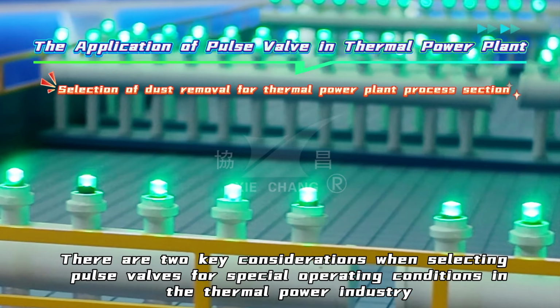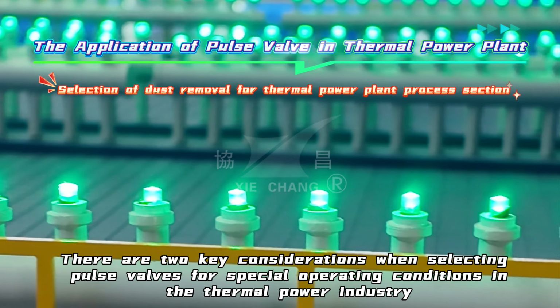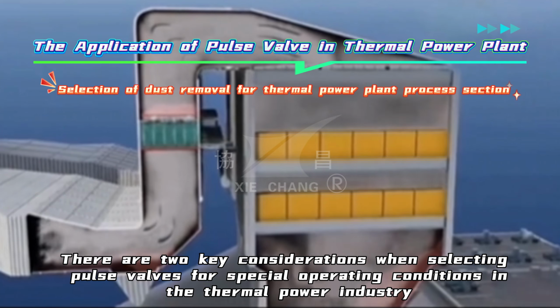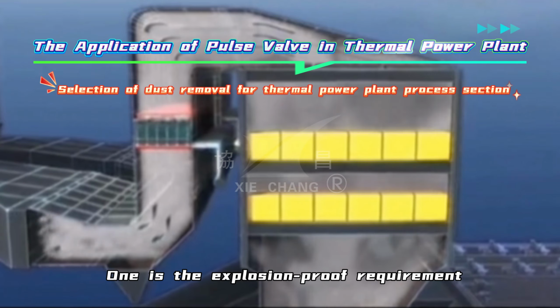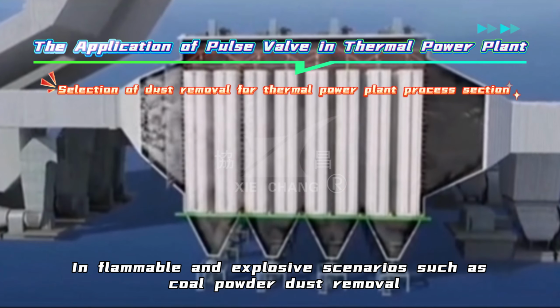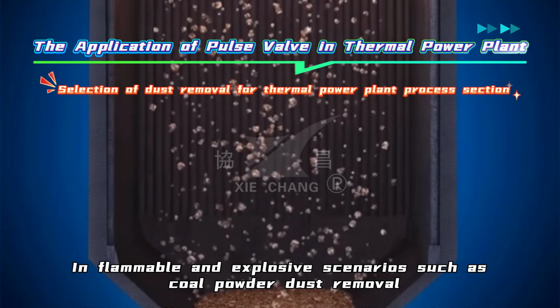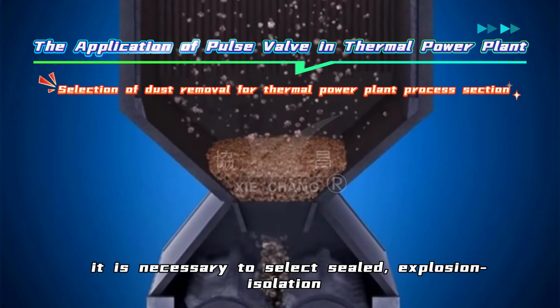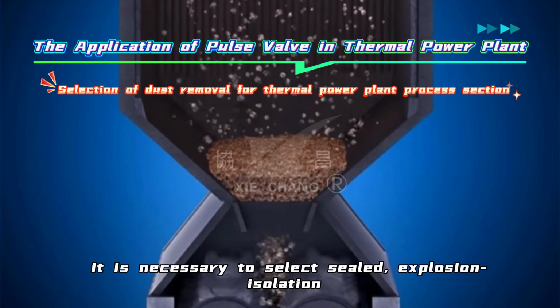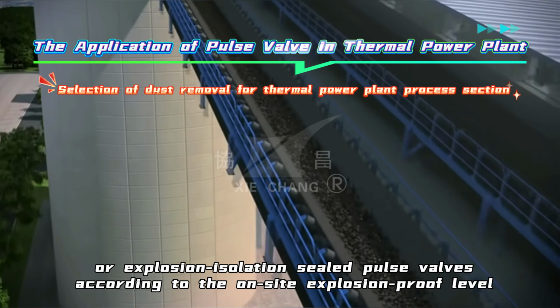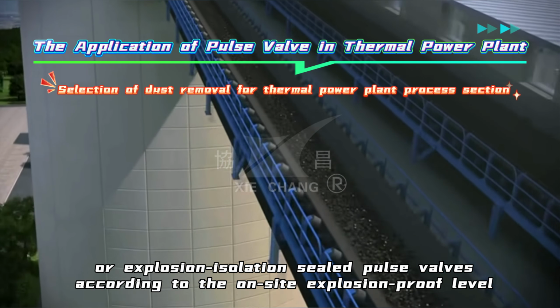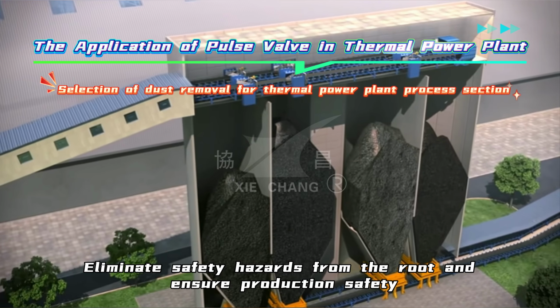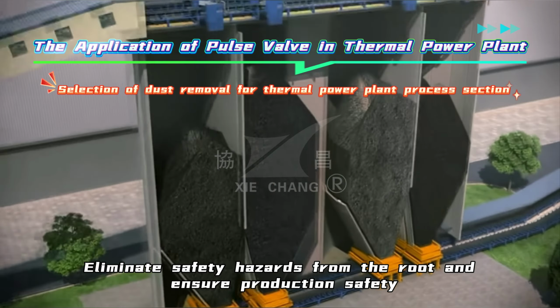There are two key considerations when selecting pulse valves for special operating conditions in the thermal power industry. One is the explosion-proof requirement. In flammable and explosive scenarios such as coal powder dust removal, it is necessary to select sealed, explosion isolation, or explosion isolation sealed pulse valves according to the on-site explosion-proof level. Eliminate safety hazards from the root and ensure production safety.